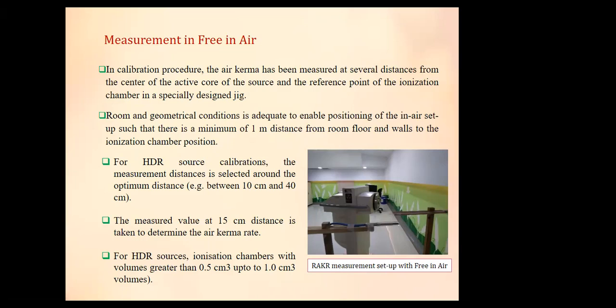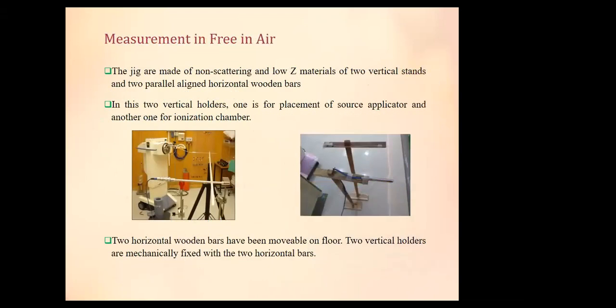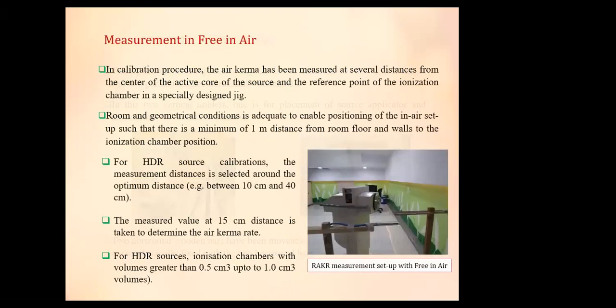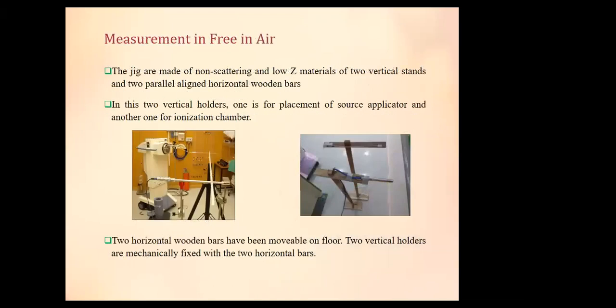For HDR sources, ionization chambers with volumes greater than 0.5 cubic centimeters, up to 1 cubic centimeter, are used. The chamber volume must be greater than 0.5 because a too small chamber volume may give problems due to lack of signal. The jig is made of non-scattering and low Z materials, with 2 vertical stands and 2 parallel aligned horizontal wooden bars. In these 2 vertical holders, one is for placement of the source applicator and the other is for the ionization chamber. The 2 horizontal wooden bars are movable on the floor.